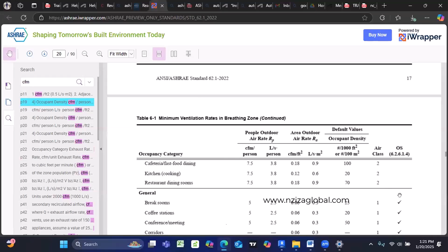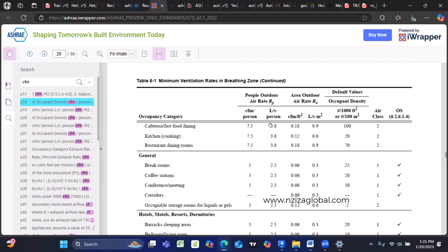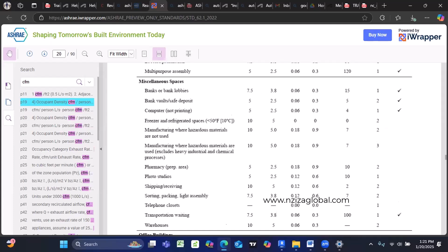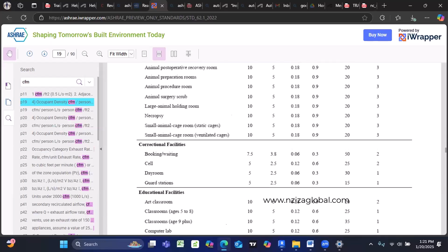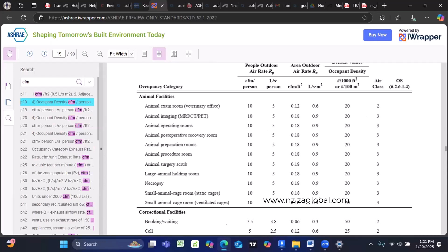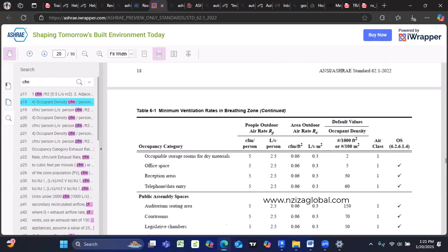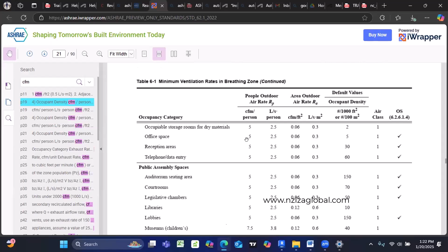For example, here, this one is ASHRAE 62.1. So we'll size the system according to the category of the building. For example, here, cafeteria or food dining requires a CFM of 7.5. And when you convert this one to metric, it is 3.8 liters per second. So different types of buildings have their own requirement, which is established by ASHRAE standards. When we come to sizing the ducts and calculating the cooling and heating loads, we'll see more how to manipulate this data.